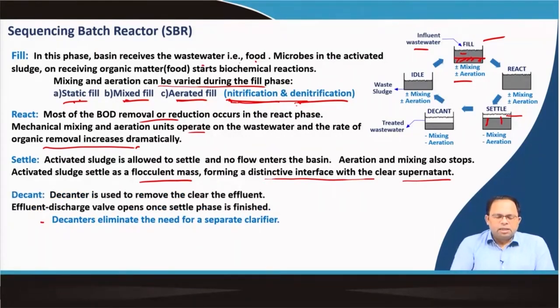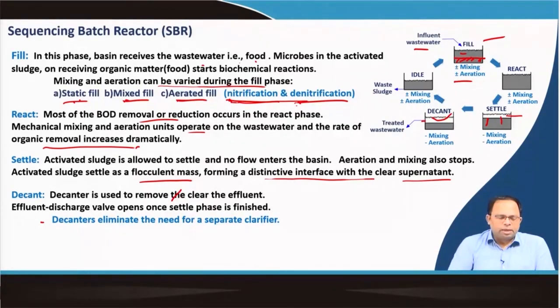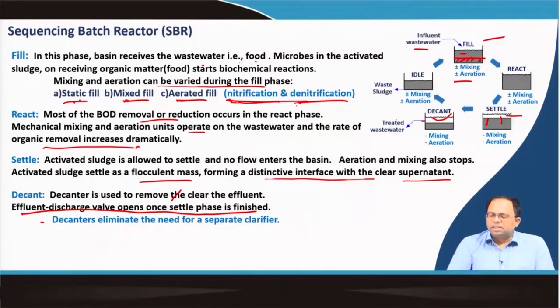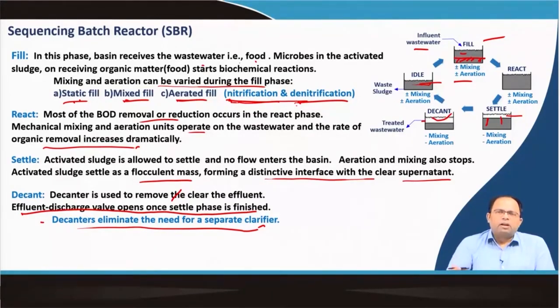In the decant phase, a decanter is used to remove and clear the effluent. We use valves at certain levels so that the upper clear liquid moves out of the chamber — the effluent discharge valve opens once the settle phase is finished. There is no need for separate clarifiers because the sludge is already settled below. Some sludge remains, but since it is almost fully digested the quantity is not that much, and we can repeat the entire process. Sometimes some sludge is also cleaned out from the chamber.